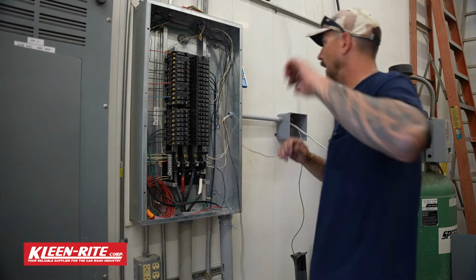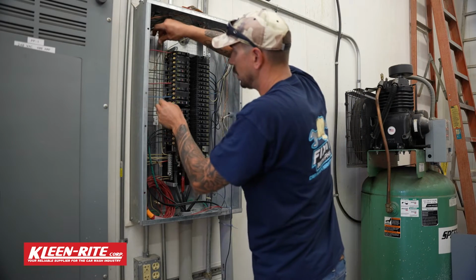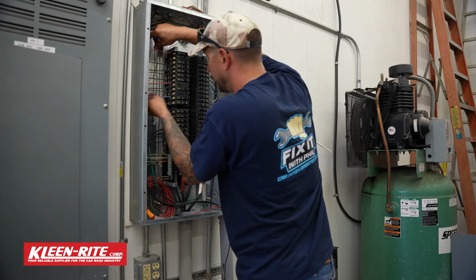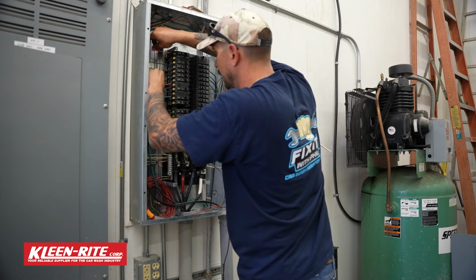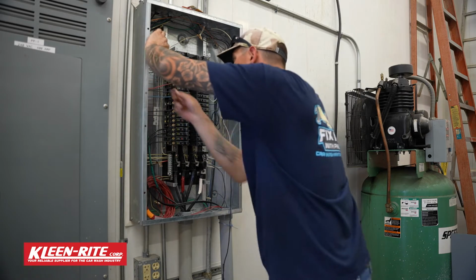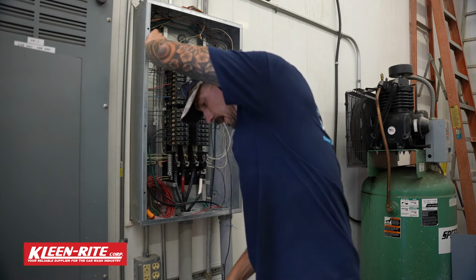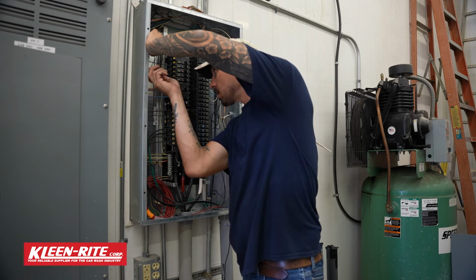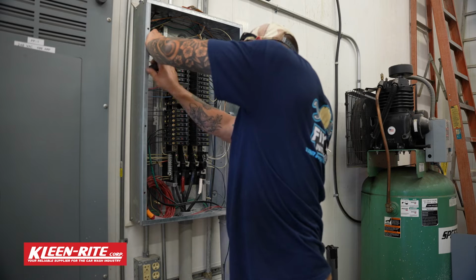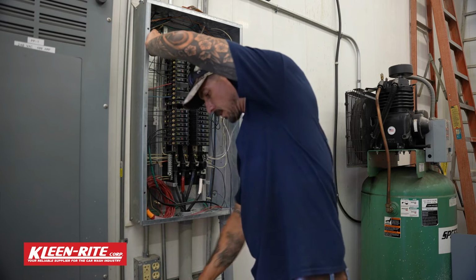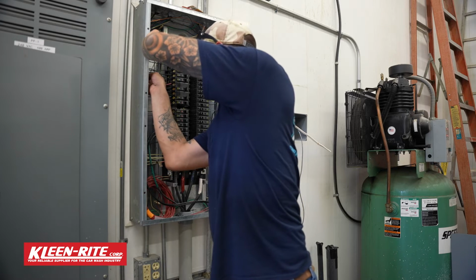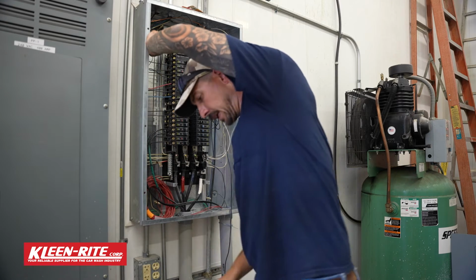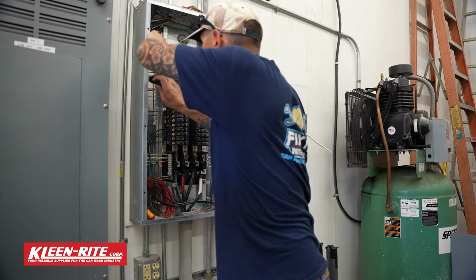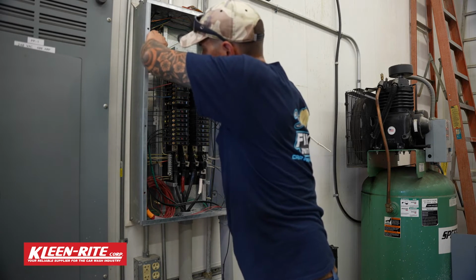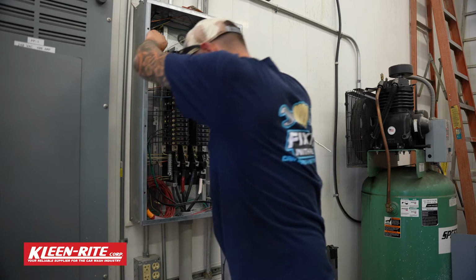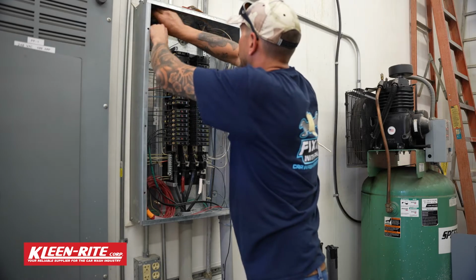Now I'm going to get this ground wire over. Again, I'm leaving enough room and enough extra wire in case something needs to be changed later, moved out of the way to add something else. It is okay to double up a neutral. It is okay to double up a ground on a lug if you're running out of space or you only have enough wire to make it to that lug. We just don't want to double up any of our hot circuits. We want all those to be separate if possible.